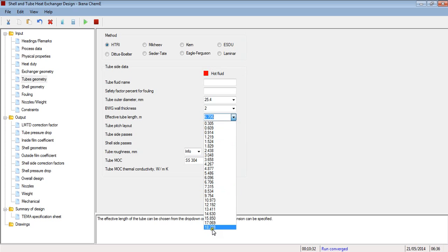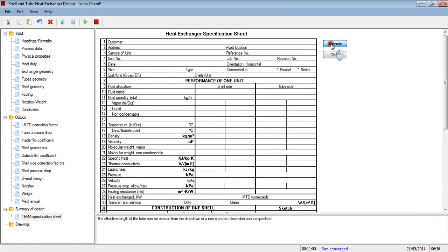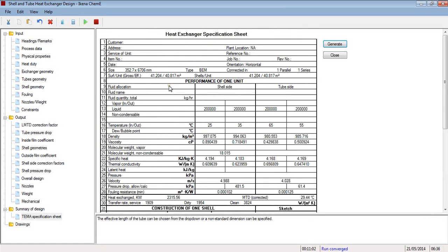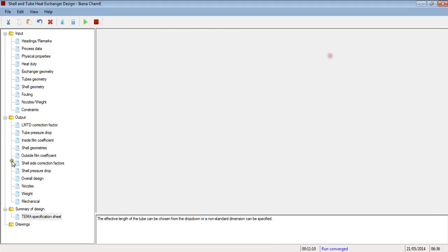Let's see, I can go up to 18 meters, but let's just assume that I do not have sufficient space, so you're limited to a heat exchanger which is 6.7 meters long. So those are the restrictions that come into the picture. So a designer needs to understand what the restrictions are and what parameters can be forced and what the effects would be. So again, if you look at this, the program can also generate a TEMA sheet for you. It has all the information required by the TEMA specification sheet. So we'll go ahead and close this.